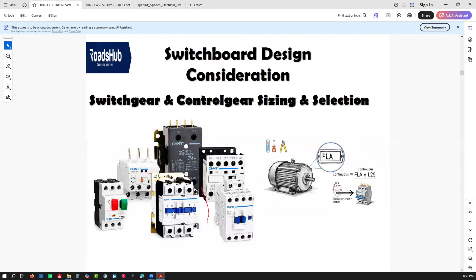Something wonderful about this system is that we have the basic elements of electrical systems, like sources. We talk about cables, we talk about components. These are the key things you'll find in all standard systems. Cables are communication pathways. When you do design work inside a switchboard, or even outside to communicate from one switchboard to another or a switchboard to a load, you need to do a lot of cable sizing and voltage drop.